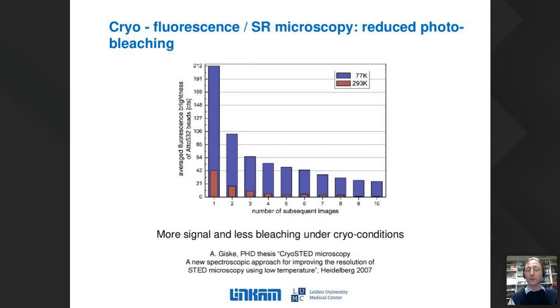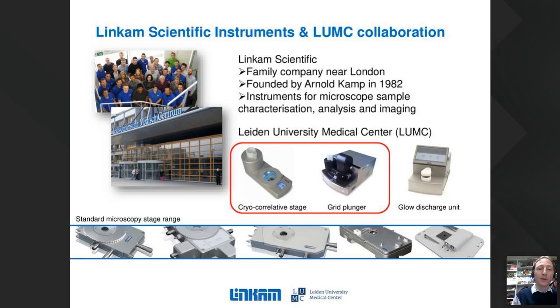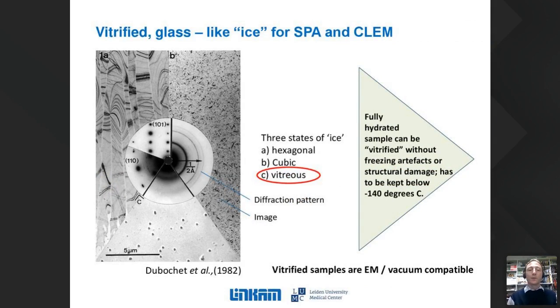Now we come to the main topic: the cryo plunger system we are developing. It's a collaboration between Leiden University Medical Center and Linkam Scientific, and we make instrumentation for cryo plunging and cryo imaging. The goal is to produce a sample with vitrified ice, requiring a very fast cooling rate on the order of 10⁴ Kelvin per second, which can be achieved with plunge freezing, typically plunging into liquid ethane.